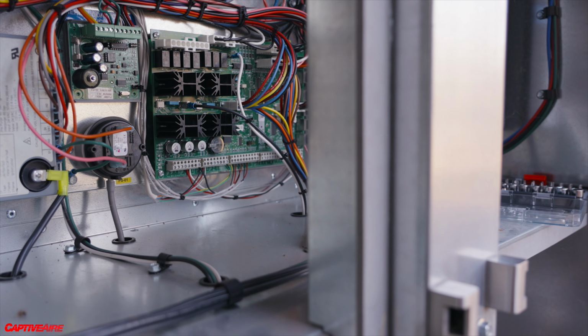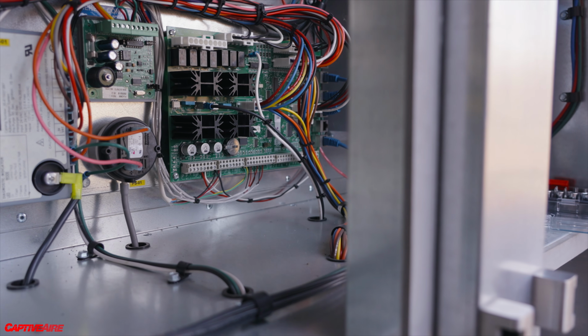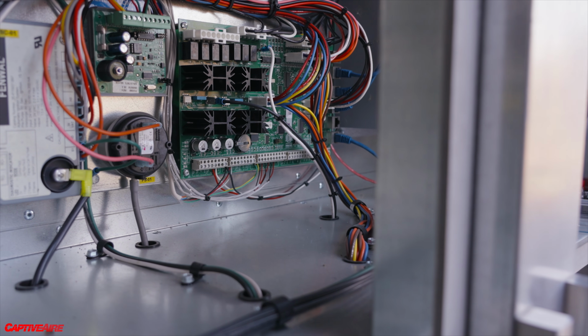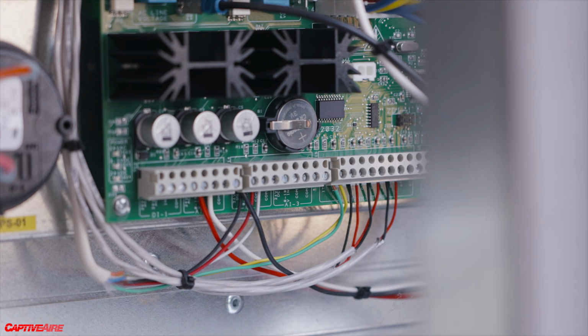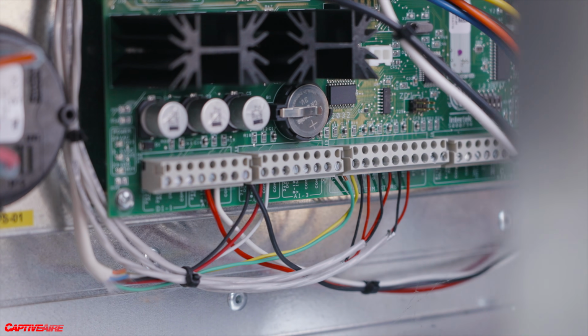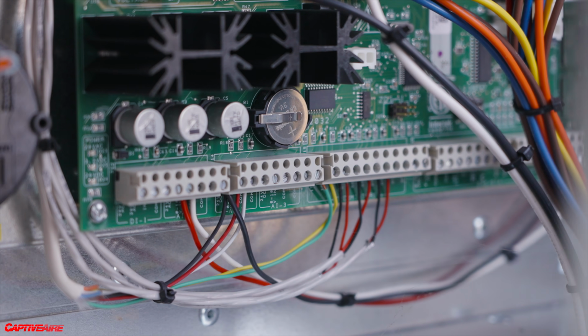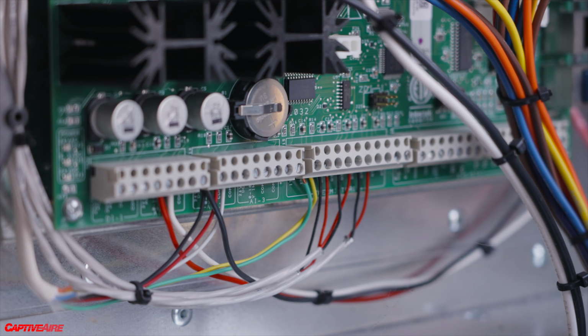So we immediately pointed our tech when they went to actually do the startup to look at the field wiring of our space sensor. And what we found is they flip-flopped and wired our humidity sensor into the space temperature side and was feeding a stray voltage back. It was skewing all the numbers. So this was a very clear cut.